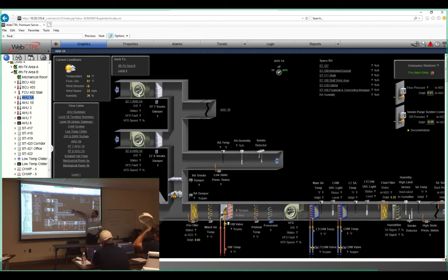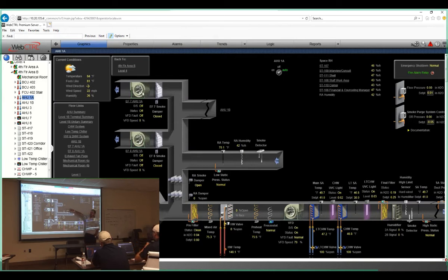So these two smoke exhaust fans get triggered by the fire alarm system from the smoke detector inside the ORs. When it gets triggered, the only thing we are doing is we have a sensor tied to these exhaust fans to try to control the pressure to negative 0.05, to make sure that the space is negative 0.05 going out, so that the smoke in the space is being exhausted.